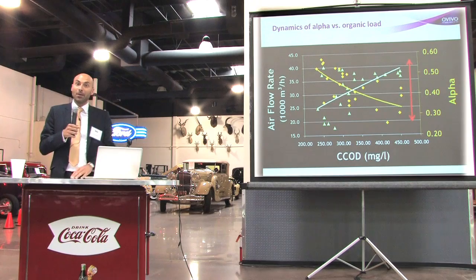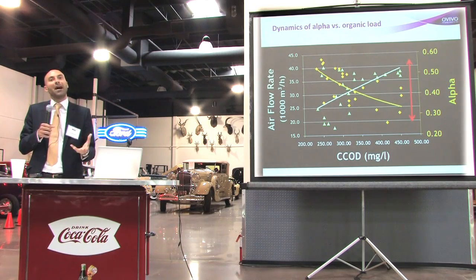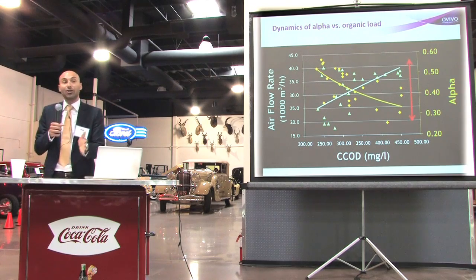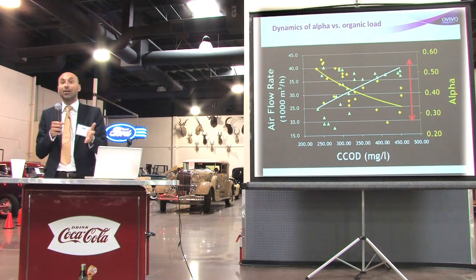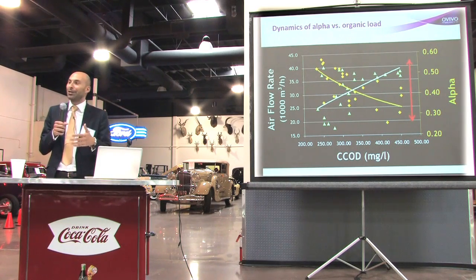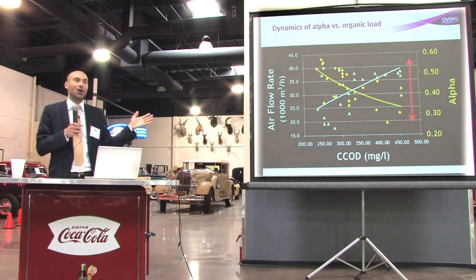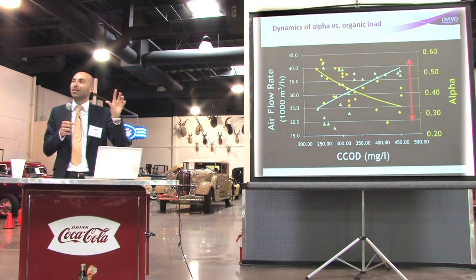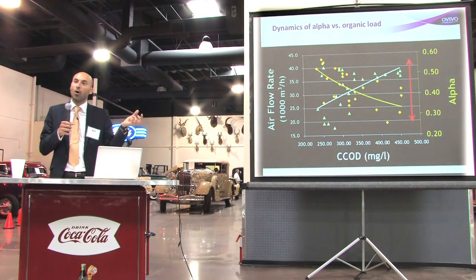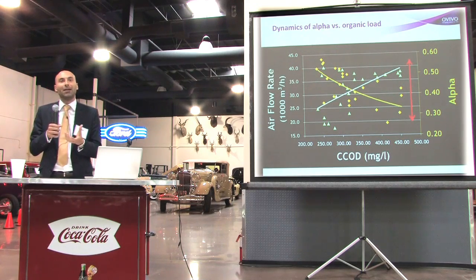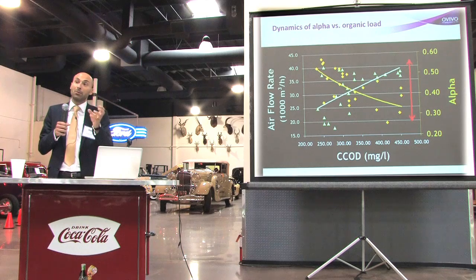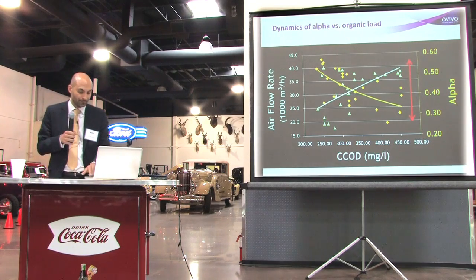Alpha goes down with higher contaminant load because more surfactants are freely available to float in the wastewater. The biomass concentration is relatively fixed over 24 hours — you can't change MLSS concentration hour to hour — but the load may change twofold, creating a highly variable amount of freely-flowing surfactants that can land on your bubbles, depressing gas transfer as Mike described: putting soap in water makes bubbles stiffer, smaller, and far less efficient at transferring gas.